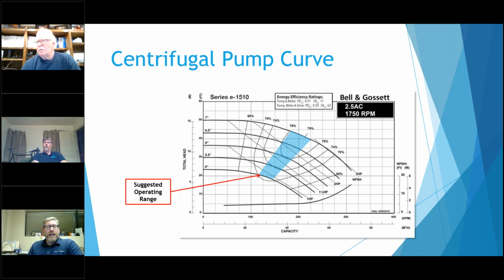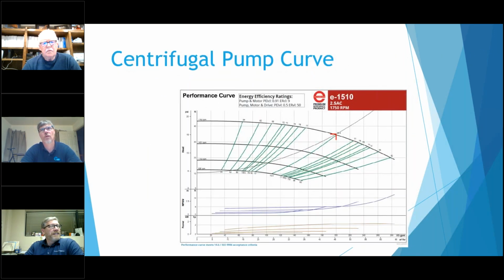So the operating range of this pump, this is the ASHRAE operating range. It's basically 85% to 105%. So this pump should be selected in that area. The acceptable range is this one here. It's a little bit larger, 66 to 115. The HI, Hydraulic Institute, is kind of this gray area here. And then we'll get to the question here.